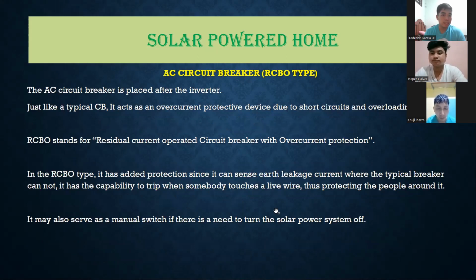Of course, we also have the AC circuit breaker, or the RCBO type. The AC circuit breaker is placed after the inverter. Just like a typical circuit breaker, it acts as an overcurrent protective device against short circuits and overloading. RCBO stands for residual current operated circuit breaker with overcurrent protection. The RCBO type has added protection since it can sense earth leakage current, where the typical breaker cannot. It has the capability to trip when somebody touches a live wire, thus protecting the people around it. It may also serve as a manual switch if there is a need to turn the solar power system off.